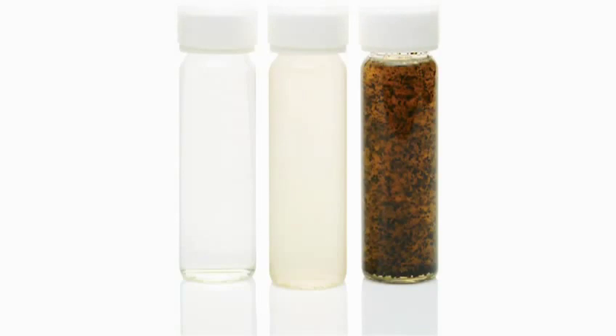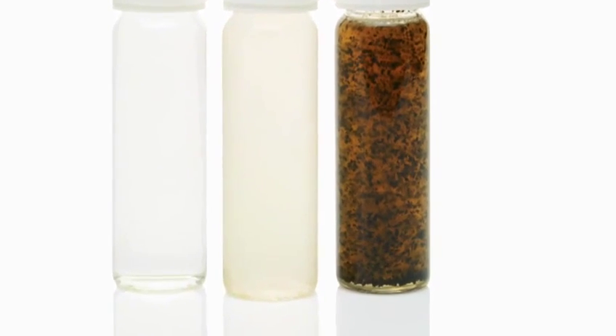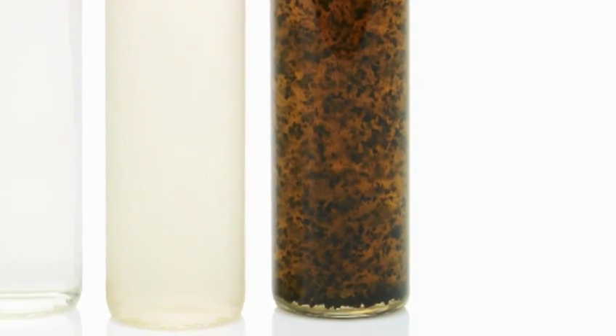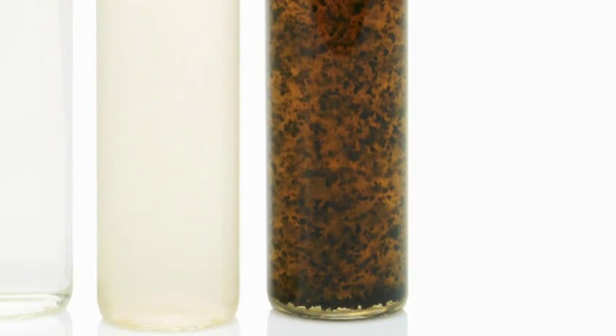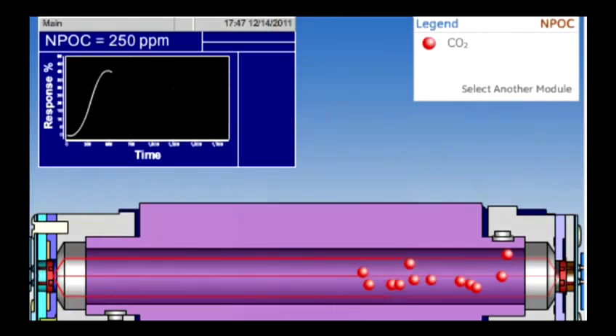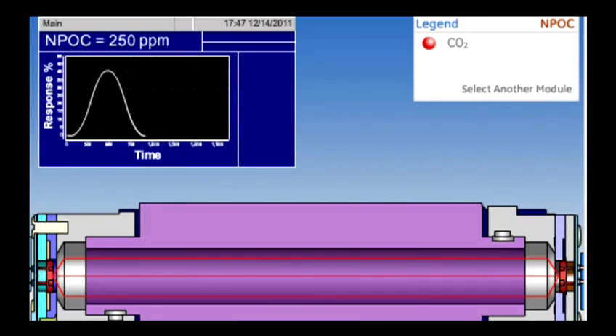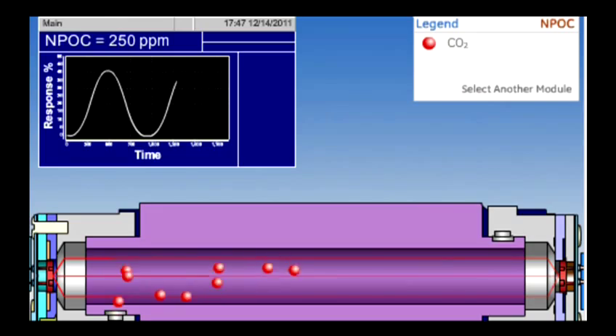The Innovox is robust. It can run thousands of tough samples, including those with brine, sugar, cellulose, and glycol with ease. The Innovox uses an NDIR detector that is immune to corrosive gases and can accurately detect up to 50,000 ppm of TOC.